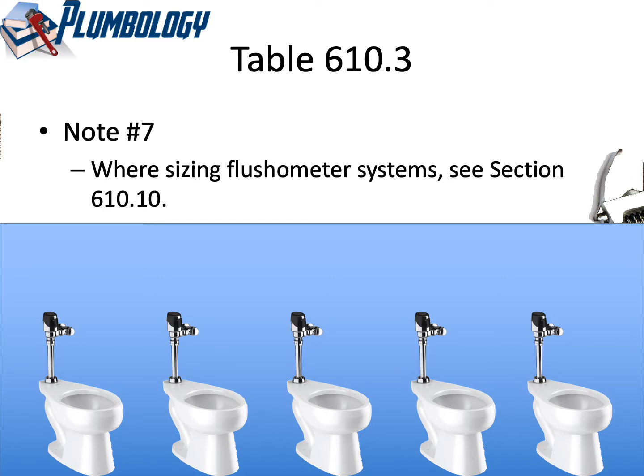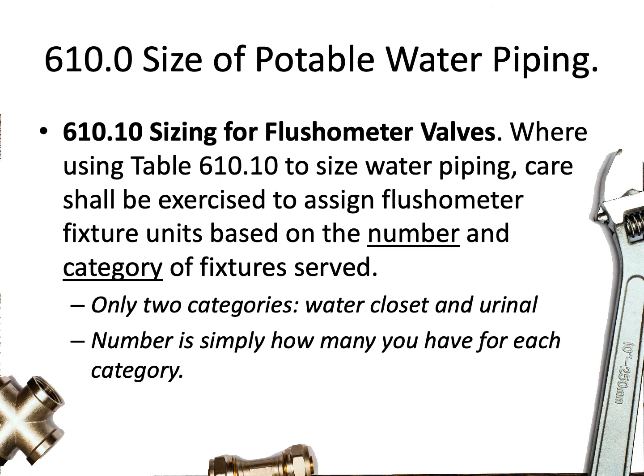Note number 7 is telling us that when sizing flushometer systems, we need to go see Section 610.10. We already looked at part of that section; next we'll look at the second half. We're using Table 610.10 to size water piping. Care shall be exercised to assign flushometer fixture units based on the number and category of fixtures being served. Here again we see that number and category language. The number part is very simple — how many do you have? Just keep counting. The category has only two options: it's either a water closet flushometer valve or a urinal flushometer valve.